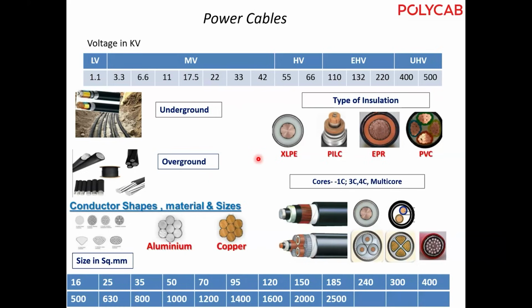Then there are different types of insulation, and cable accessories should be as per the type of insulation. XLPE is extensively used in India now for insulation. Then PILC type of cables. These cables are no longer manufactured right now, but in India, many places still have old PILC cables buried. Whenever those cables fail, the customer uses a transition joint at that place. So one side is PILC, another side is XLPE, and in that case we require a special type of joint. That's a transition joint. Then EPR cables, PVC cables, these are the different types of cables.